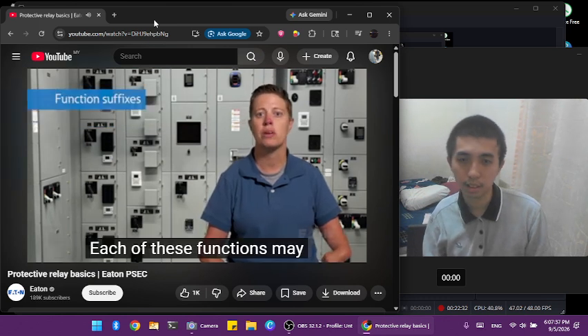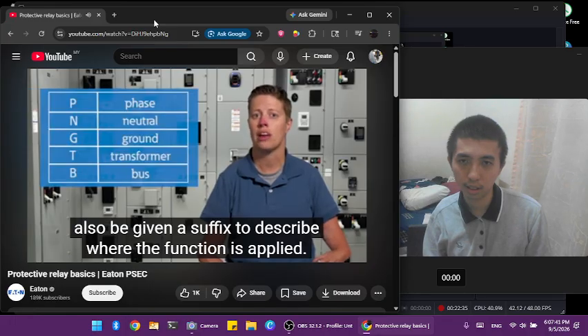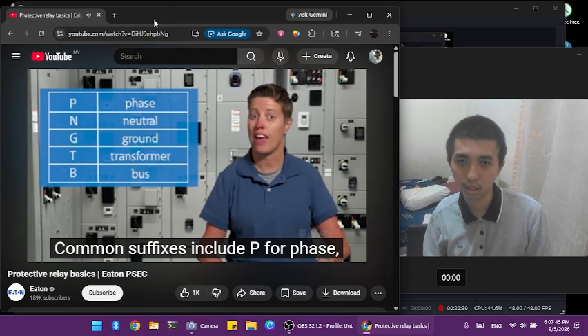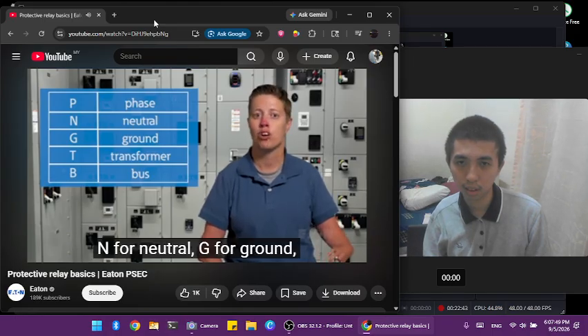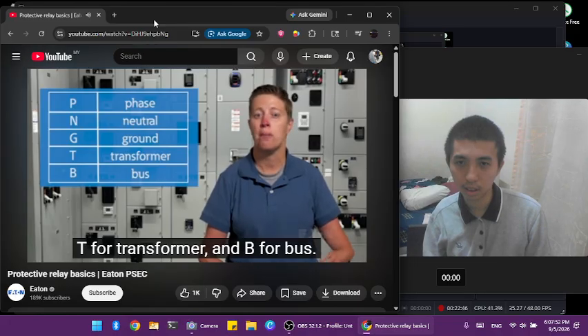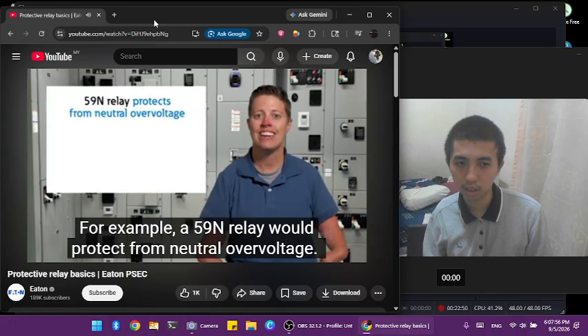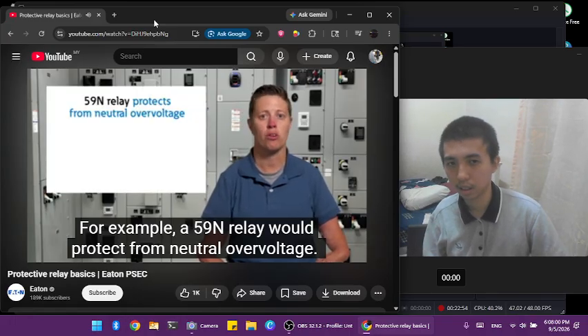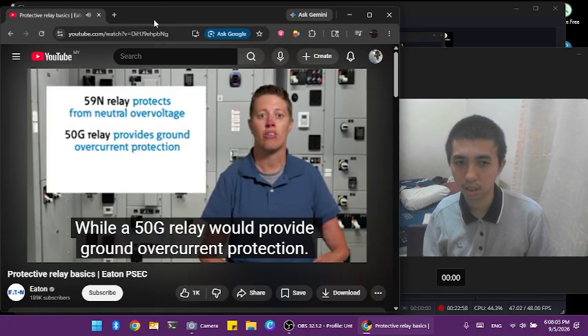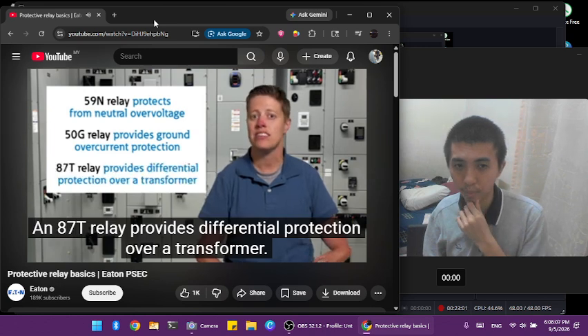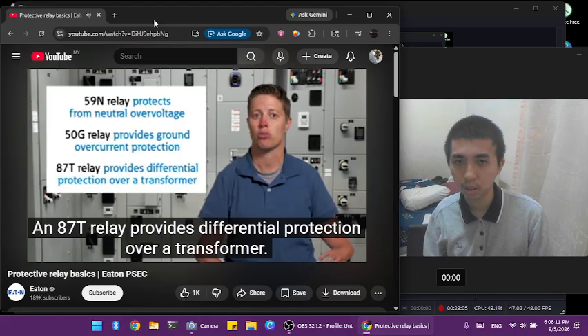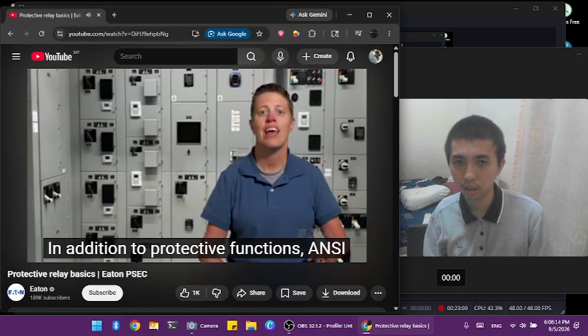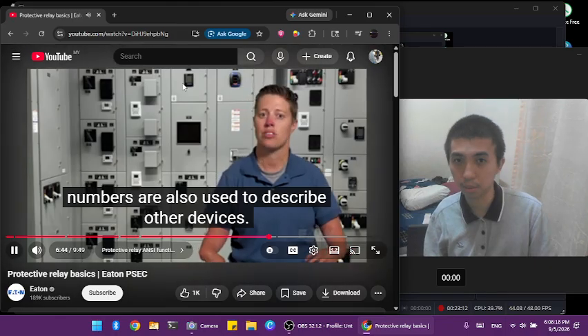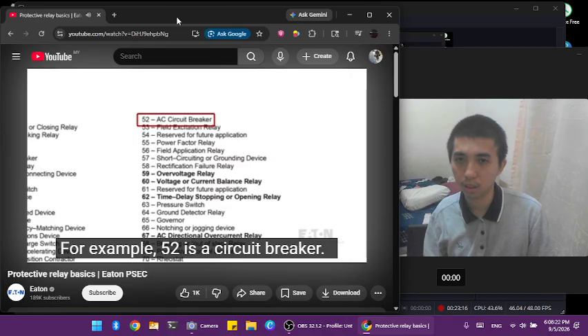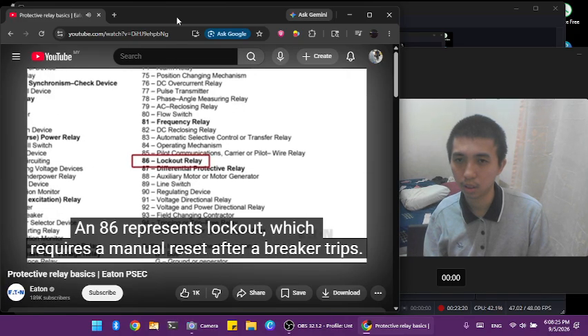Each of these functions may also be given a suffix to describe where the function is applied. Common suffixes include P for phase, N for neutral, G for ground, T for transformer, and B for bus. For example, a 59N relay would protect from neutral overvoltage, while a 50G relay would provide ground overcurrent protection. An 87T relay provides differential protection over a transformer. In addition to protective functions, ANSI numbers are also used to describe other devices. For example, 52 is a circuit breaker, and 86 represents lockout, which requires a manual reset after a breaker trips.